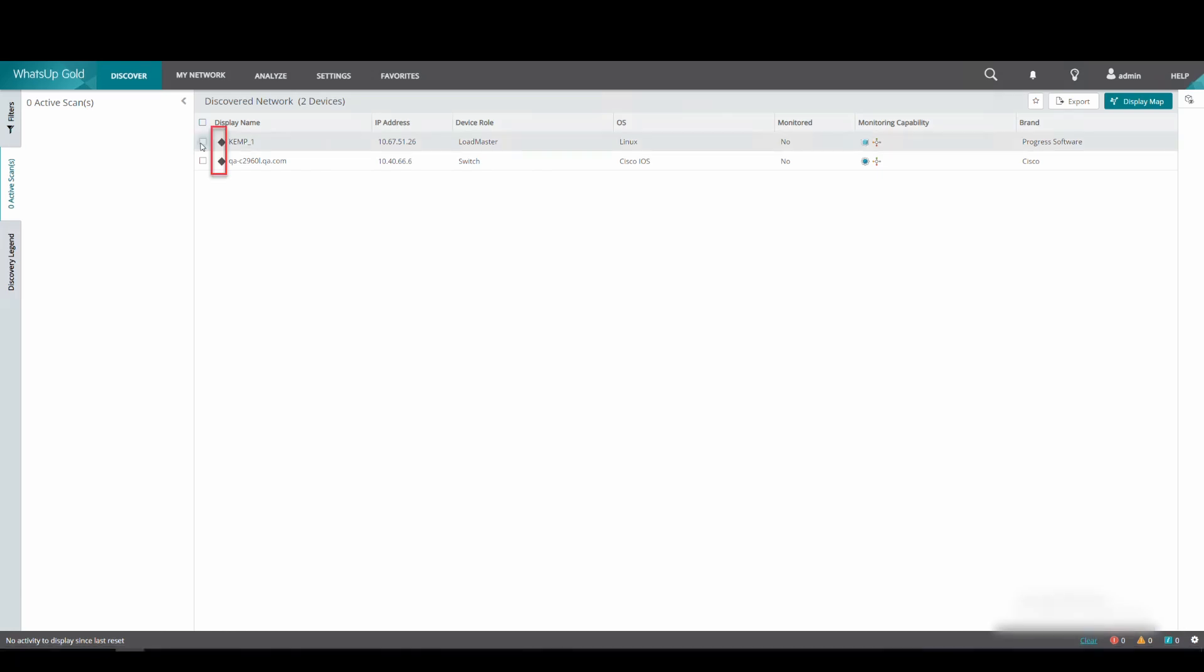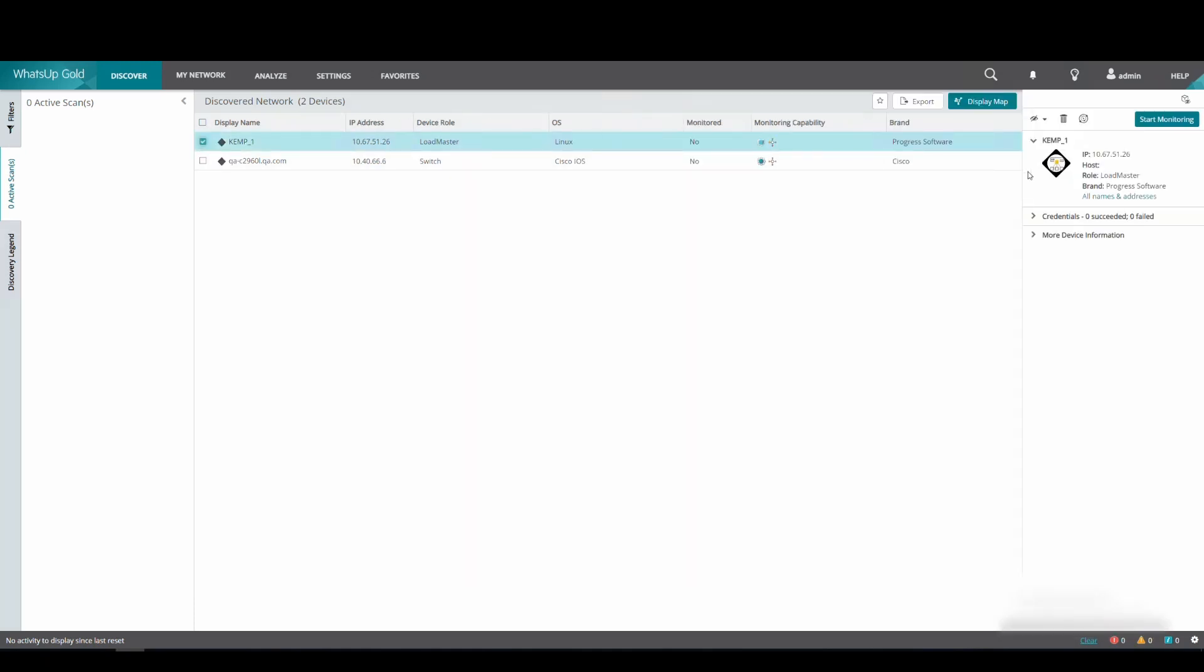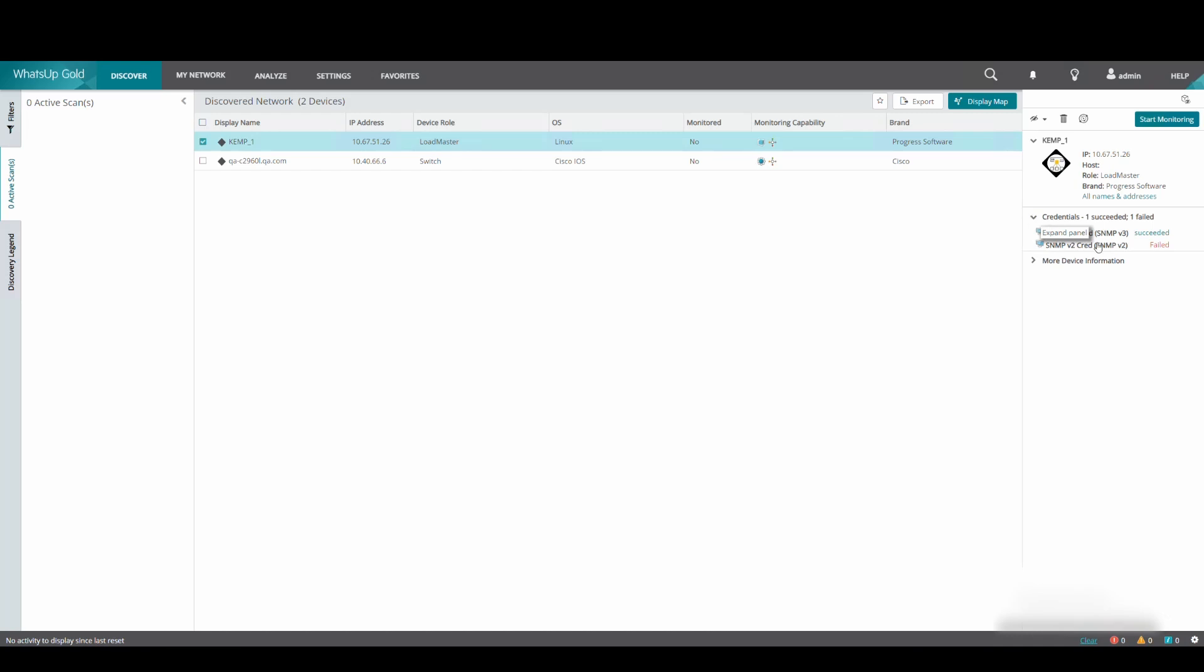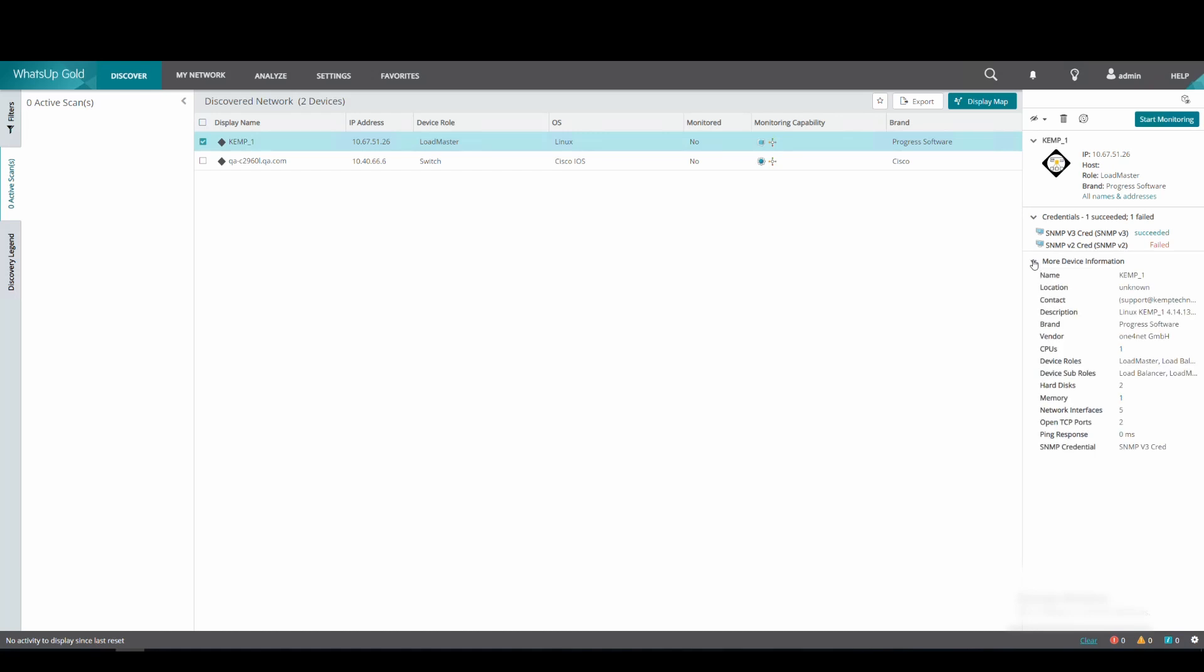We can see the black diamond symbol beside the devices, which indicates that they are not monitored. By selecting the first device in the list, the loadmaster device, we can see that the SNMP v3 credentials succeeded, and the SNMP v2 credentials failed. And we can see additional information about the device underneath.